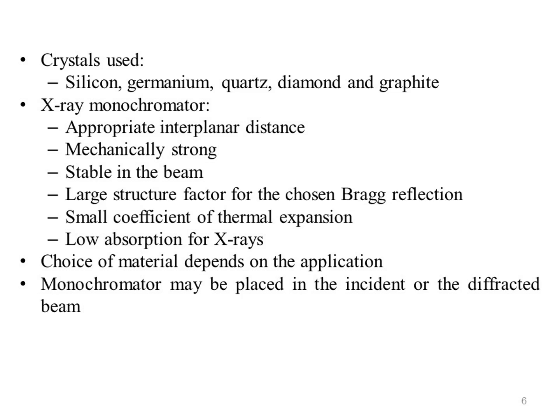The actual choice of material also depends on the application and may take into account the thermal conductivity, degree of crystalline perfection, intrinsic breadth of the Bragg reflection, which is the Darwin width, etc. In the laboratory, a monochromator may be placed in the incident or the diffracted beam.